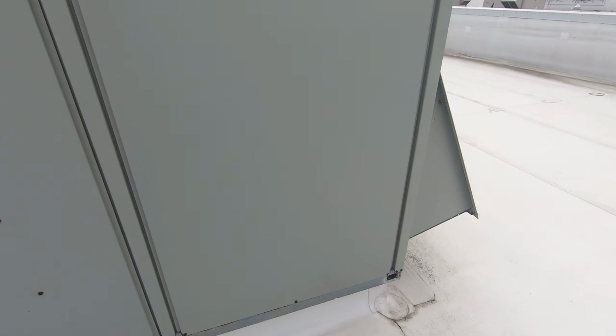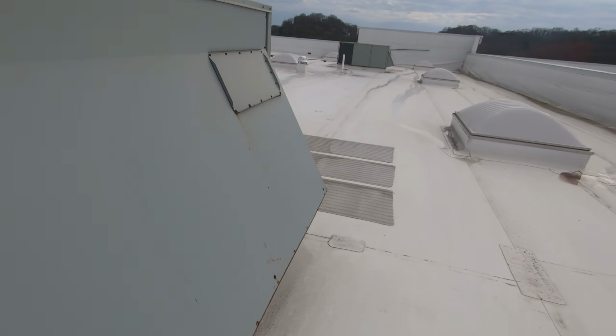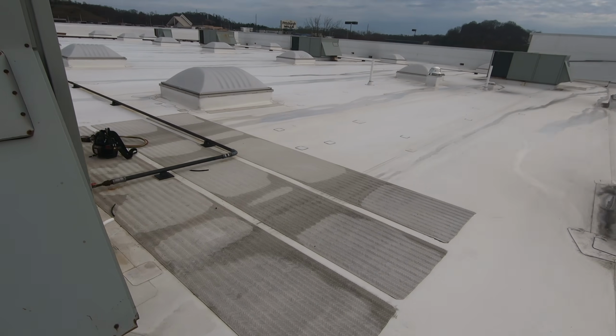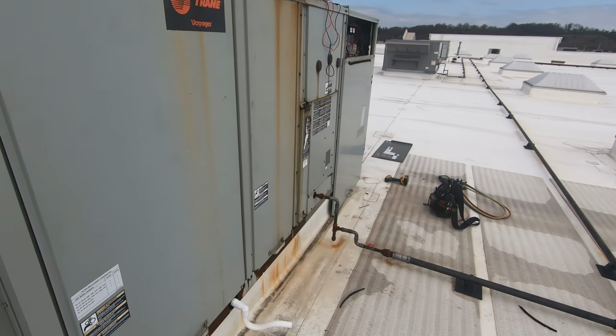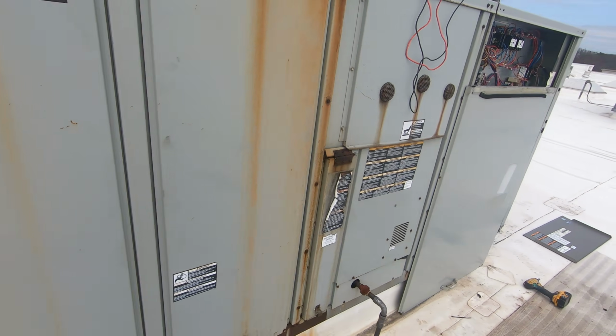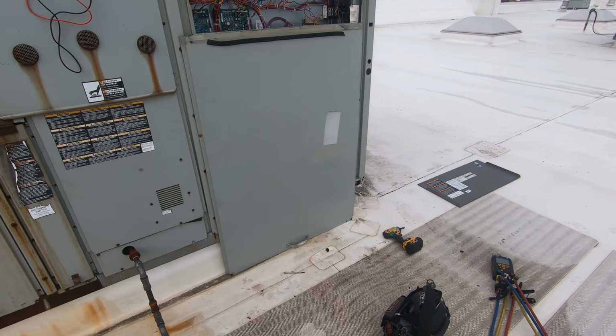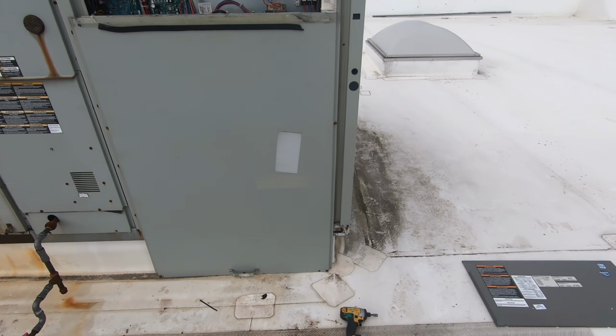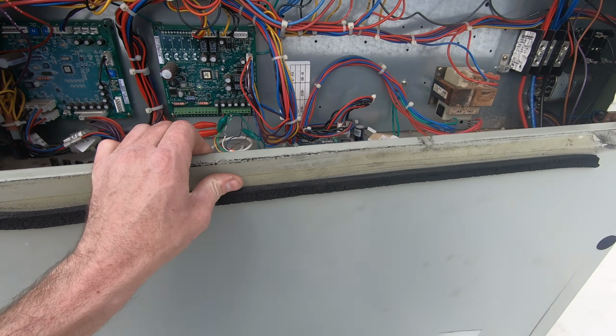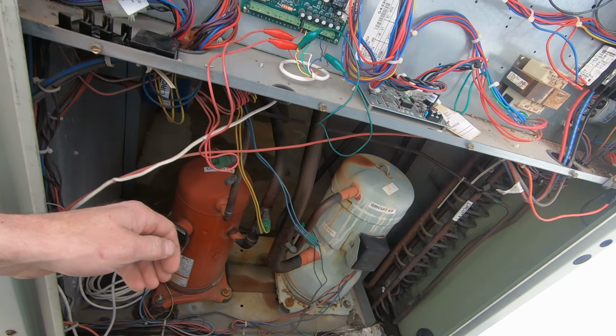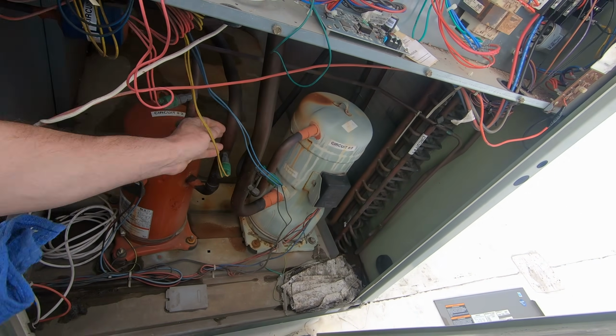Wait for second stage to come on. Give it the old suction line touch. Make sure it's good to go. Open up this blower compartment. Check that blower belt. Make sure the blower's running the right direction. All right. Second stage is on. Oh yeah.